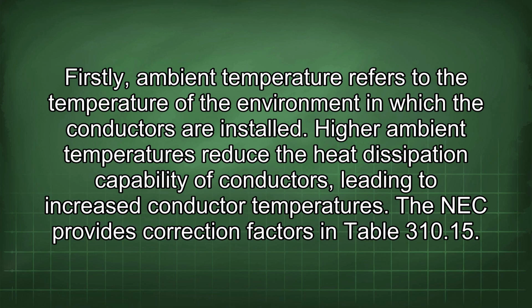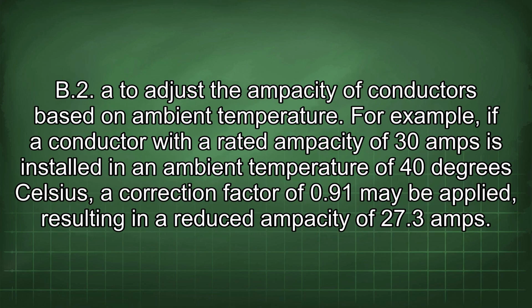The NEC provides correction factors in Table 310.15(B)(2) to adjust the ampacity of conductors based on ambient temperature. For example, if a conductor with a rated ampacity of 30 amps is installed in an ambient temperature of 40 degrees Celsius, a correction factor of 0.91 may be applied, resulting in a reduced ampacity of 27.3 amps.